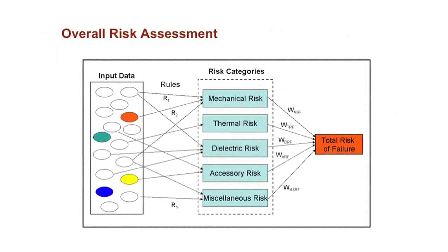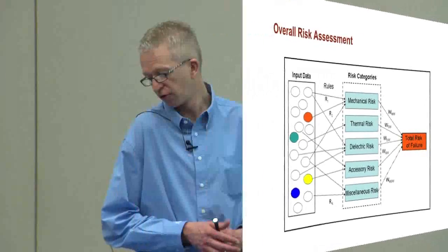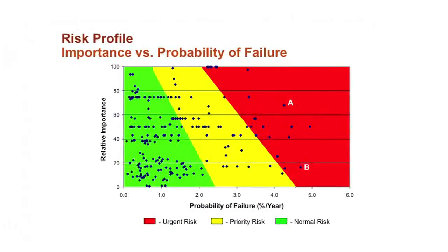Okay, so then we calculate all these different individual risk factors, using all the different input data, and then you get a total risk of failure. After you have each individual risk of failure, you can calculate the overall risk of failure for a whole fleet. This shows as an equation how risk of failure is calculated. Again, we look at what it was designed with, what it saw in the environment it was in, and then the present condition. And then you calculate the overall risk of failure. For us, we have this all in a special tool. The input for our tool is all Excel based, and the tool applies all the different rules, calculates all the different risks of failure, and then we get an output chart like this.